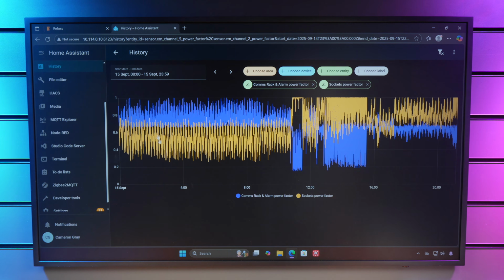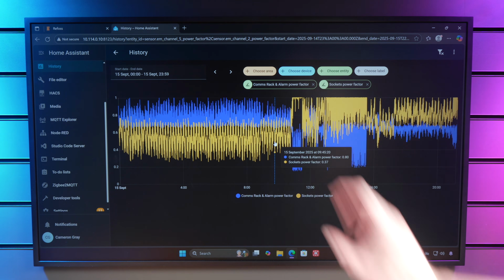The socket circuit is tracking a little bit lower than the comms rack, which is probably roughly expected, and overnight when there's not much socket usage, power factor is a little bit lower than the comms rack, and they're both wildly fluctuating, but in sort of the same lanes.